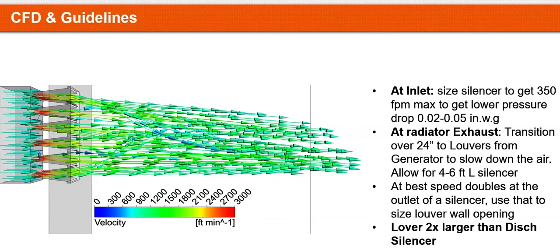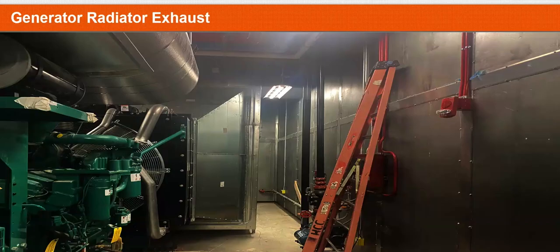A couple of pictures of some installed applications. You can see right here that in this case, they decided to transition before they went into the silencer so that after the silencer, they have a longer transition to slow down the air. In this case, once it exited, it was about 1,000 feet per minute leaving the silencer. Also showcasing that the opening at the top has silencers on the vertical because you're trying to treat all the lines of sight, not just one.